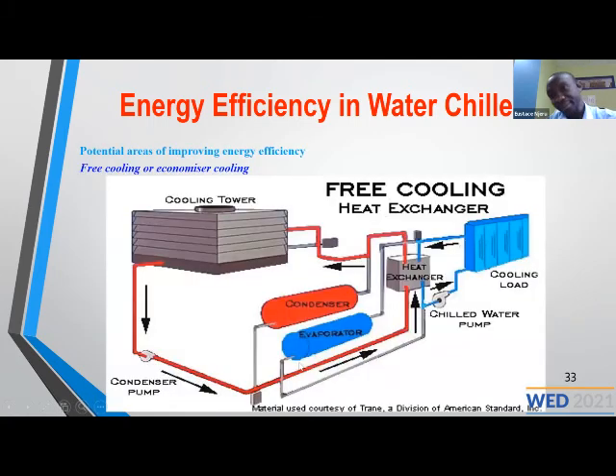This is what we call free cooling. In a normal situation, the cooling tower is supposed to cool the condenser in the water chiller. And the evaporator cools the chilled water being used in the cooling load. So the circuit originally is supposed to flow, for example, the chilled water is supposed to go to the evaporator, then go back to the cooling load. Then the water from the cooling tower is supposed to go to the condenser.